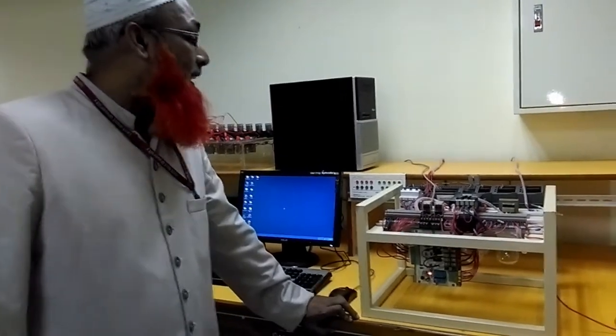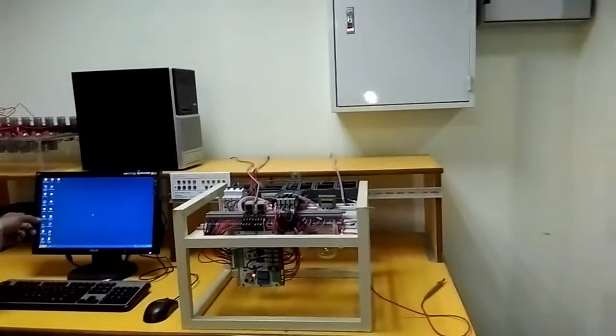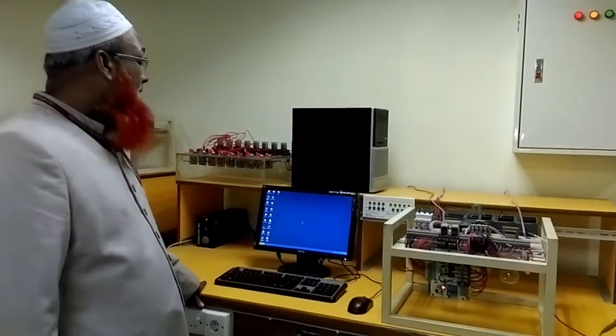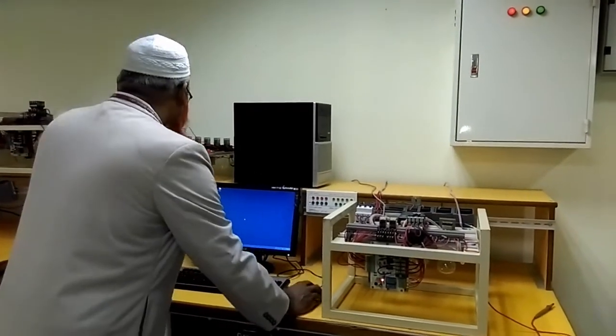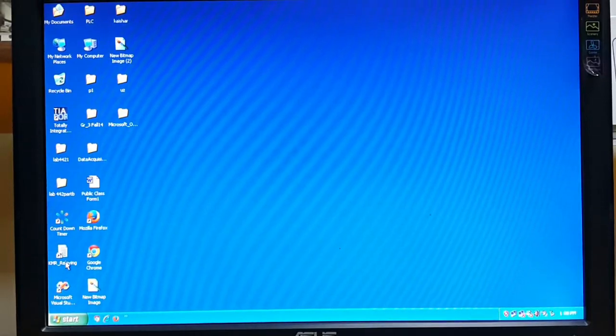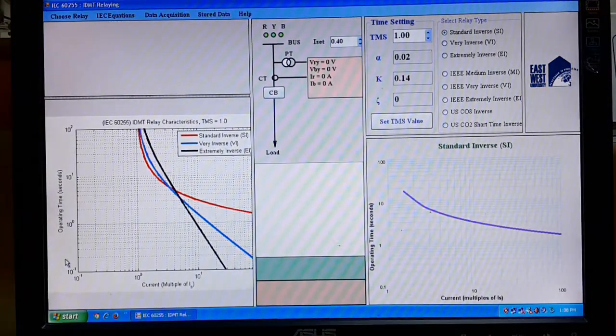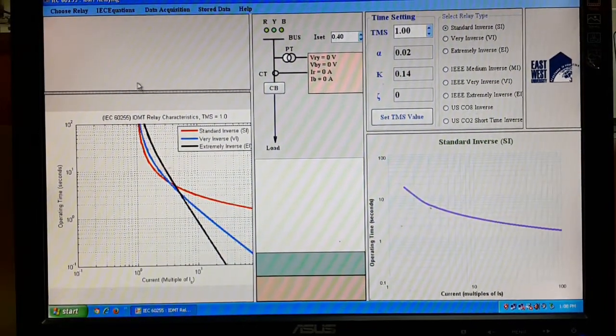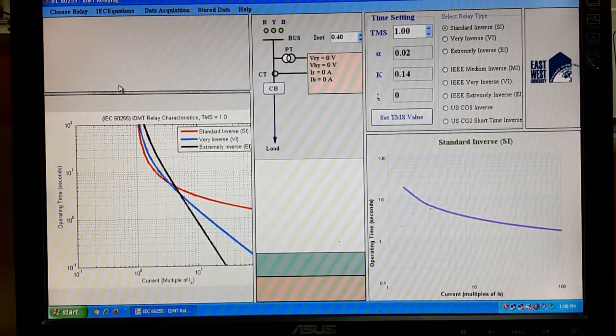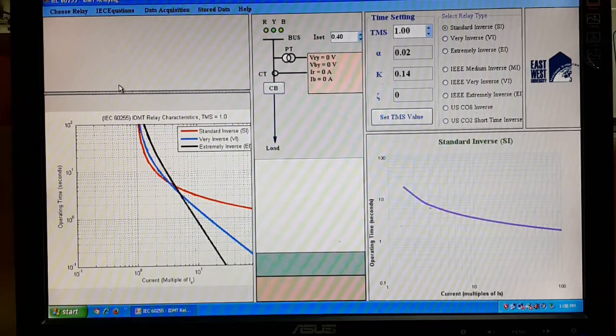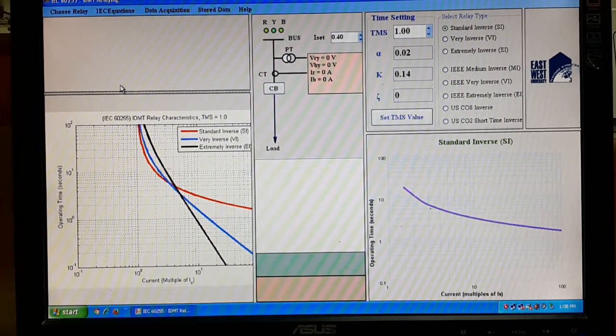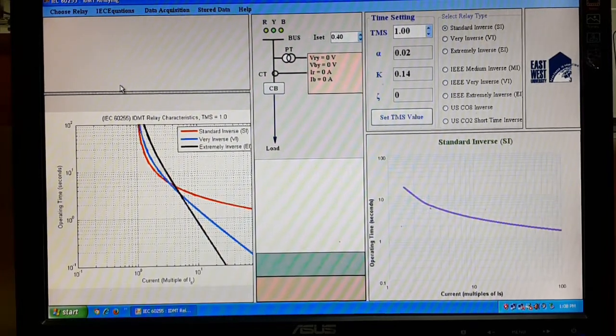These voltages and currents are sent through this data collection module to the computer. We have a software called KMR Relay that has all the interfaces for the numerical relay. When you start this software, the initial windows appear. The graphical interface has two parts: the left side shows theoretical curves and equations for all over-current relays, and the right side has the online interface.